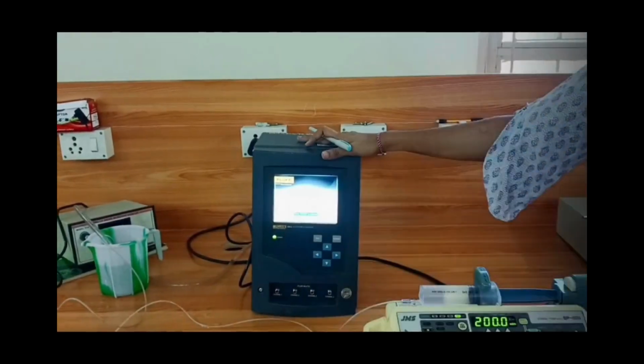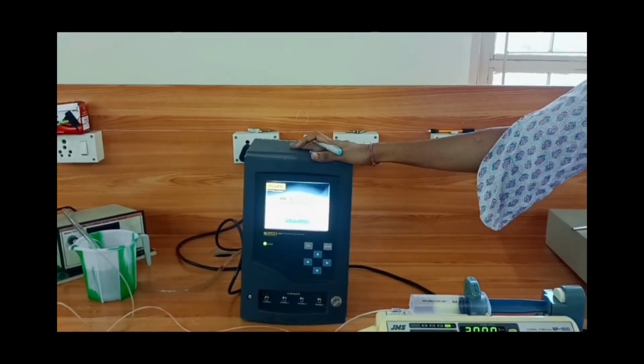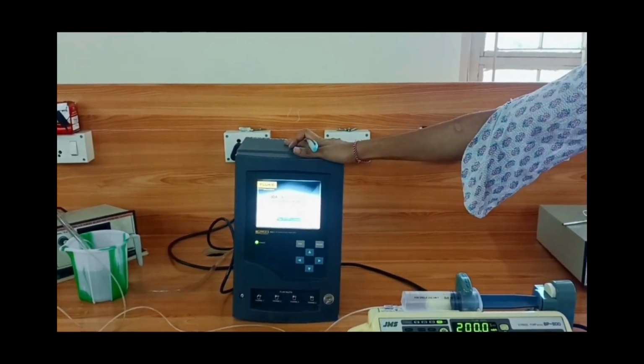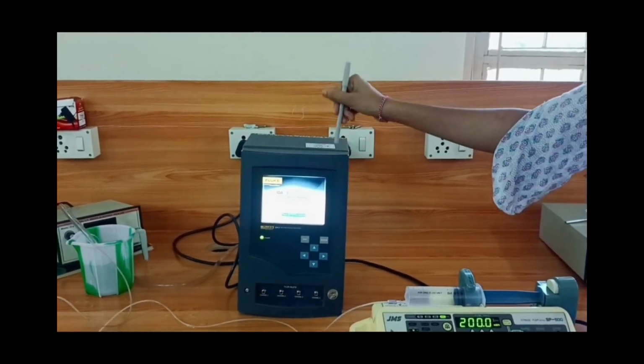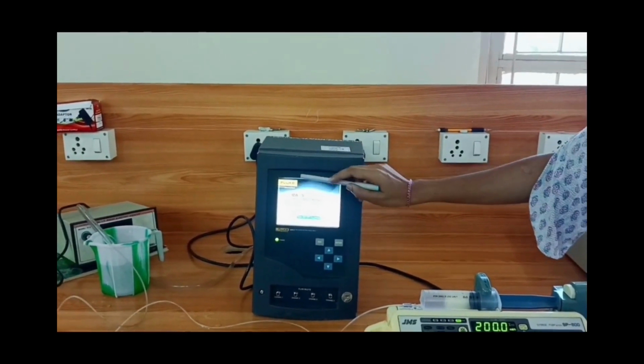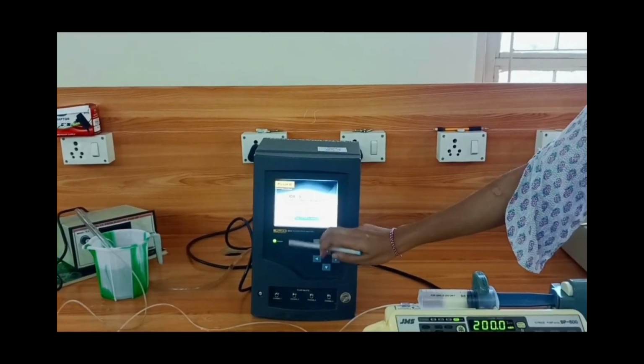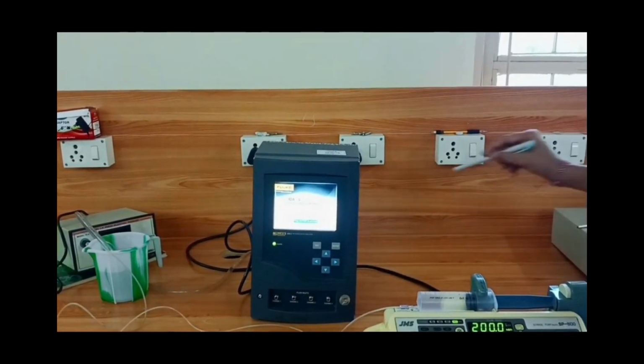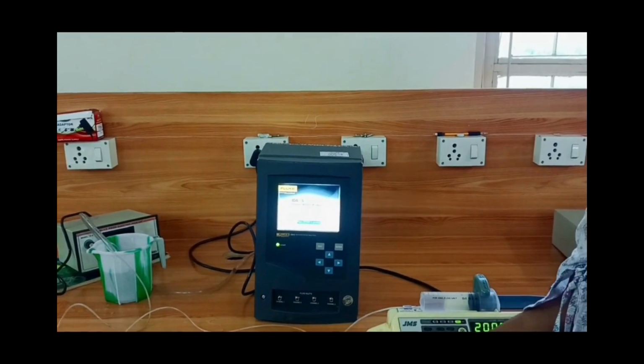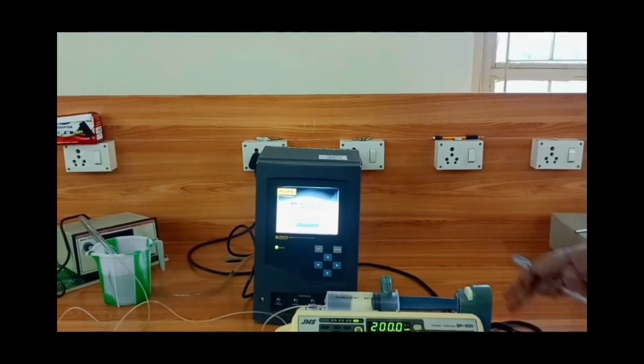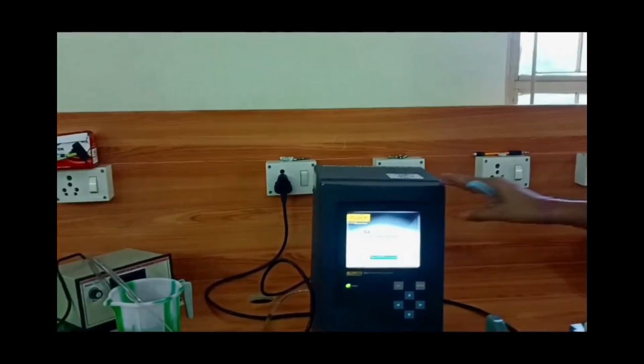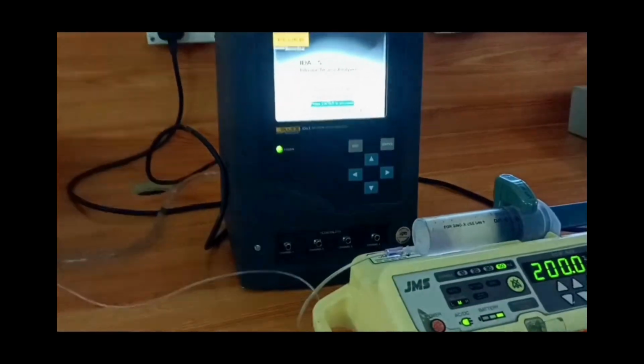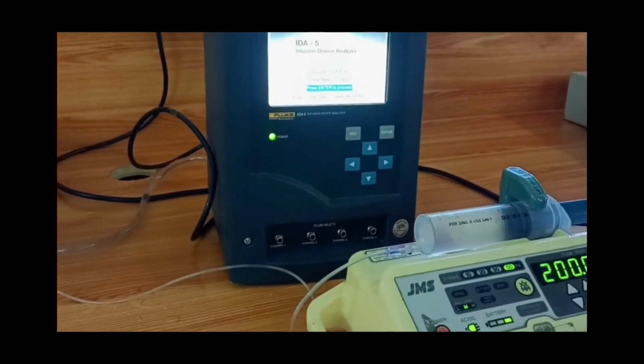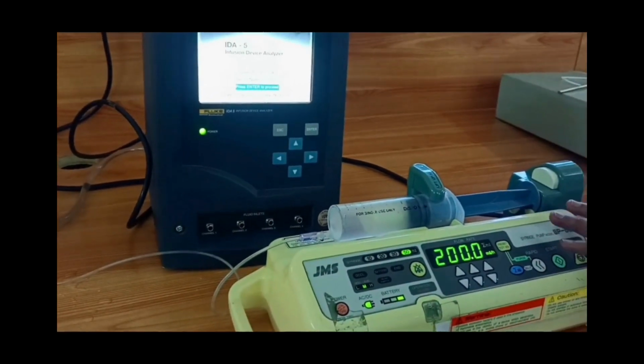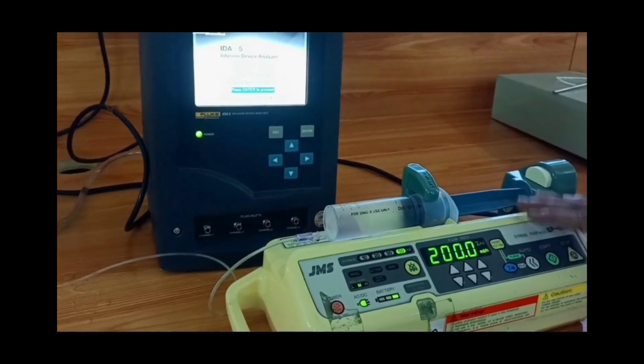This is the infusion device analyzer which is used to calibrate the syringe pump as well as the infusion pump. This is manufactured by the company Fluke and the model number is IDA5. It has 4 channels. Now let us look at the connections of the syringe pump with the calibration device. Now I am calibrating the syringe pump. Till now we have seen how the syringe pump works. Now we are seeing how we should calibrate the syringe pump.